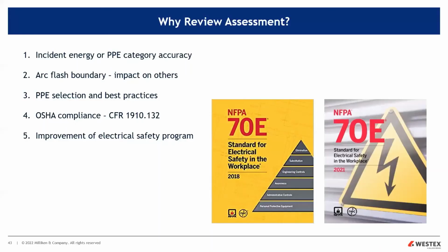So in summary, to wrap up real quick, you've got to make sure it's accurate. The incident energy has got to be correct, or the PPE is not going to be correct. Can you use the PPE category? Have the changes changed where you have to go to the incident energy method? The boundary, has it changed? It may impact others, especially if you're in a task-based program.